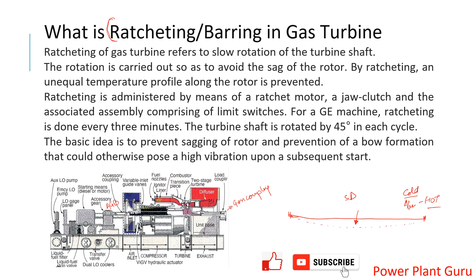If there is this kind of bow and you start the machine, it will behave like this — rather than rotating in a straight line, the rotation will be in a bowed path, with one side as the top and the other as the bottom of the shaft. This kind of thing will cause high vibration or rubbing of the shaft or rubbing of bearing white metals.